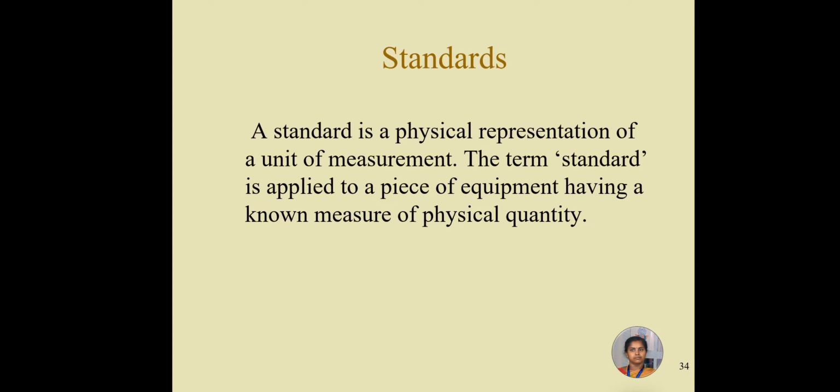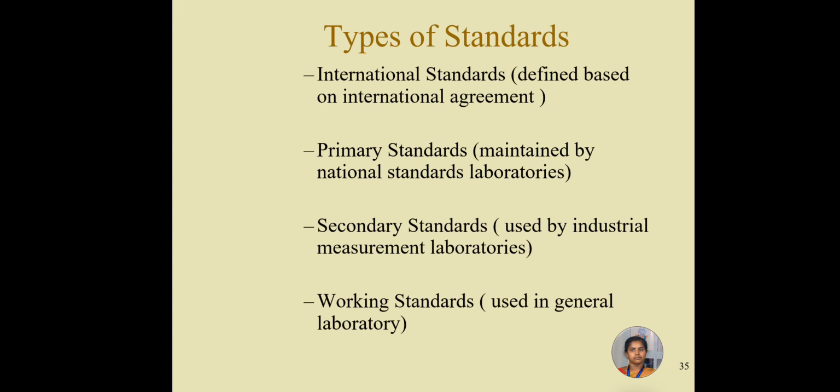A standard is a physical representation of a unit of measurement. The standard is applied to a piece of equipment having a known measure of a physical quantity. The types of standards include international standards, defined based on international agreement; primary standards, maintained by the national standard laboratories; secondary standards, used by industrial measurement laboratories; and working standards, used in general laboratories.